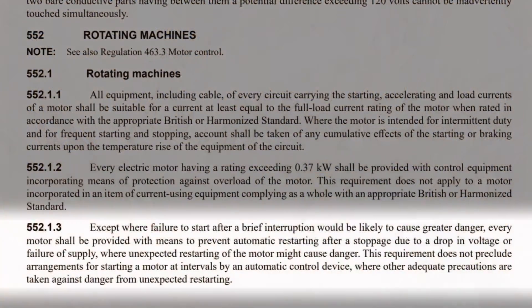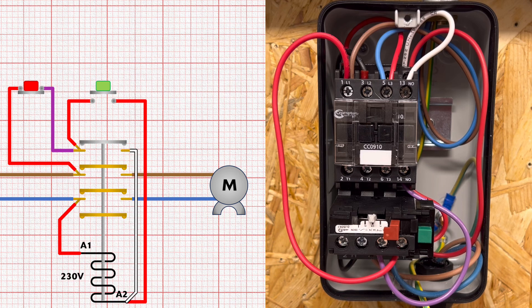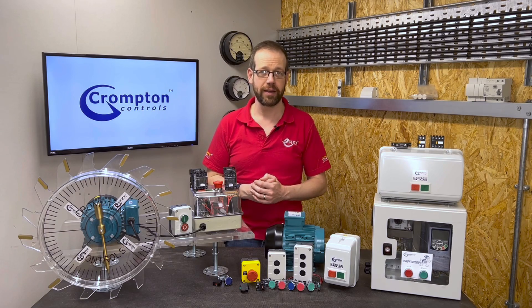At the start of the video we discussed regulation 552.1.3, which basically states that if the power is cut to a motor, it shouldn't be able to restart suddenly when the supply is restored. Looking at the way we've got this direct online starter wired up, pressing the stop button stops the motor and it won't restart until the start button is pressed. But exactly the same thing will happen if we disconnect the external supply to the starter — the coil will drop out, disconnecting the auxiliary contact, and if the external supply is then reconnected it won't restart until we press the start button. This means we've complied with the regulation.